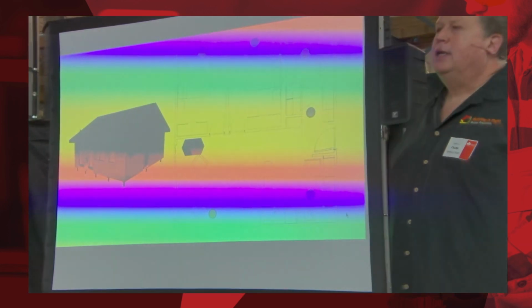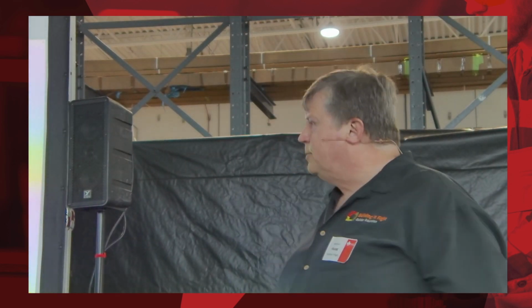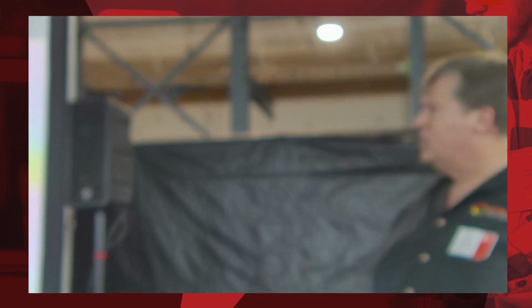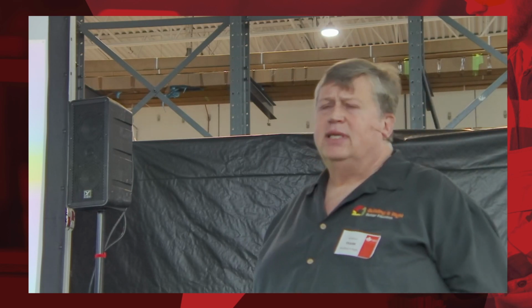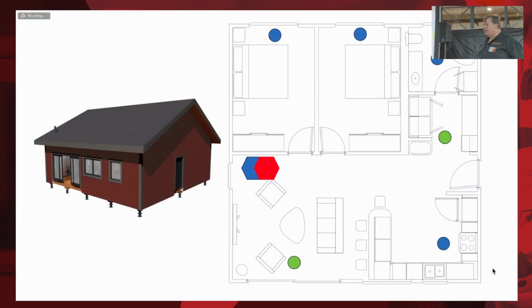We're going to have one cassette only in the entire house—a mini split, one head, huge COP of 3.9. It's an 18,000 BTU unit that'll comfortably hum at 12,000, producing all the heating and cooling we need. We adjusted the window spec for solar gain; it's such a low percentage of glazing on this that solar heat gain wasn't really a factor, but I'll show you the impact of rotating this northeast, south, and west.